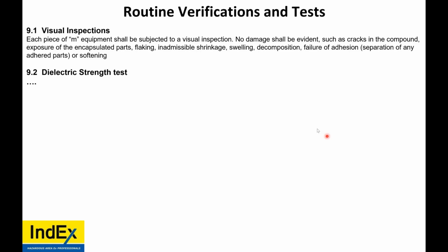If you have an IP66 gland and an IP66 Ma device, if you don't install an IP washer, you're actually going against the standards. You think you're meeting the standards, but you're going against the certificate, the manufacturer's IOMs, and the standards. Everybody bought an IP66 device, and you have now caused it to not be IP66. You're allowing potential water to ingress later on in its life.